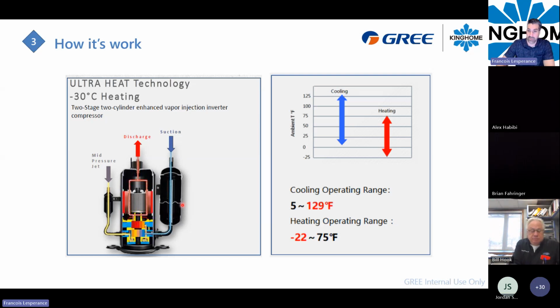So this diagram is just to let you see how the vapor injection occurs, mixing with the suction pressure right here. This is a two-stage rotary compressor, and by mixing that pressure together, that will increase our discharge pressure going out from the compressor. So this is why at -30 we still have a high heat operation with those kind of units.